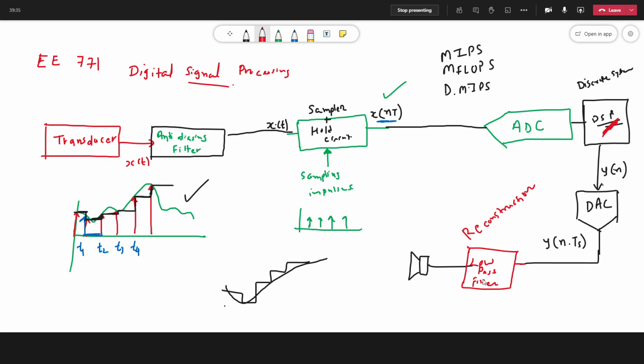And if RMS calculated will be higher than certain value, certain threshold value, we say pickup current or pickup setting, then DSP processor will trip the circuit breaker via certain mechanism of NONC contacts and tripping coil.